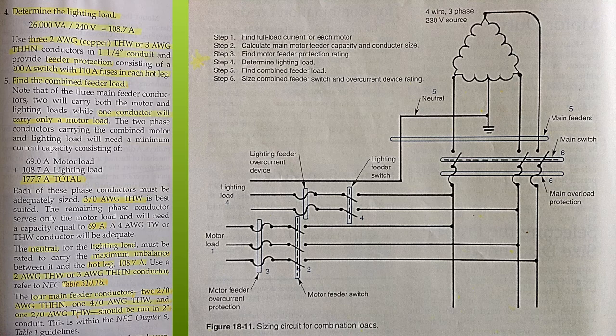Each of these phase conductors must be adequately sized. In this case, 3/0 AWG THW is best suited. The remaining phase conductor serves only the motor load and will need a capacity equal to 69 amps. A 4 AWG TW or THW conductor will be adequate. The neutral for the lighting load must be rated to carry the maximum unbalance between it and the hot leg, or 108.7 amps. So use a 2 AWG THW or 3 AWG THHN conductor. For this, refer to NEC table 310.16.